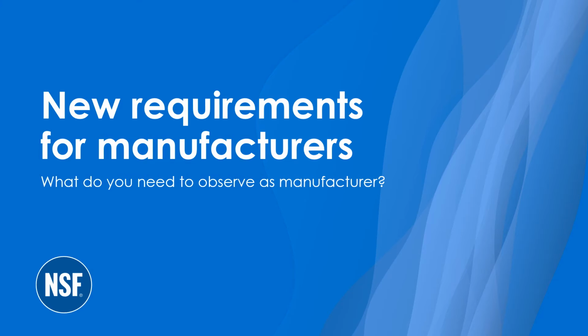Now let's assume you identified the risk class your product falls into, and you got also a first idea of what will be included in the conformity assessment so that in the end you can declare conformity to the IVDR successfully. As you may have seen, all risk classes have in common that the IVDR demands a technical documentation and a full quality management system. Now let's have a look at what is demanded from manufacturers when compiling the technical file and establishing a QM system for the IVD product.